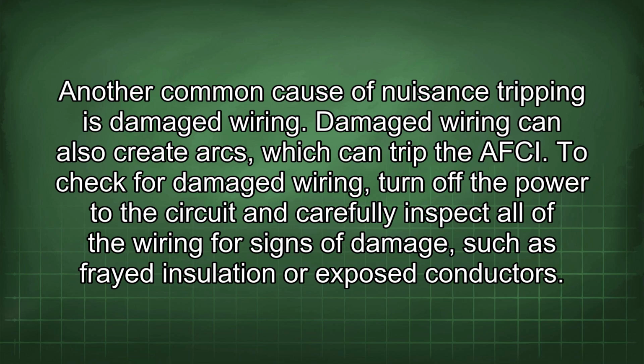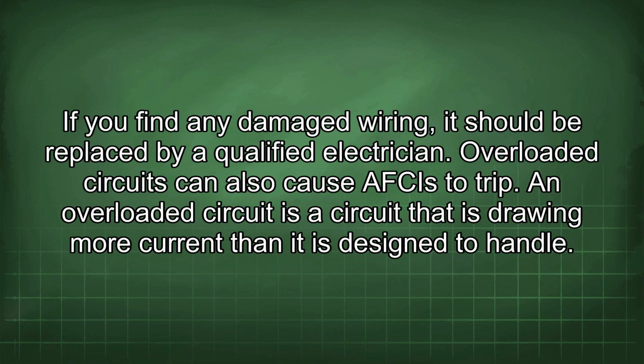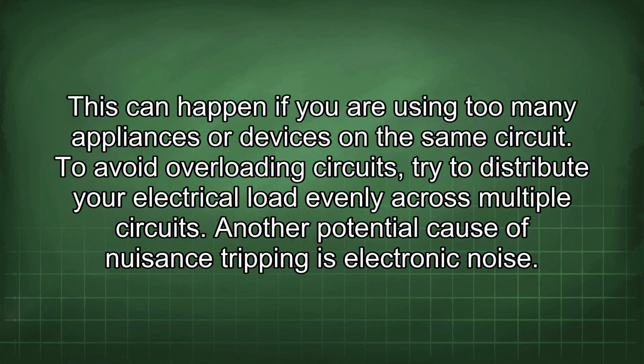To check for damaged wiring, turn off the power to the circuit and carefully inspect all of the wiring for signs of damage, such as frayed insulation or exposed conductors. If you find any damaged wiring, it should be replaced by a qualified electrician. Overloaded circuits can also cause AFCIs to trip. An overloaded circuit is a circuit that is drawing more current than it is designed to handle. This can happen if you are using too many appliances or devices in the same circuit. To avoid overloading circuits, try to distribute your electrical load evenly across multiple circuits.